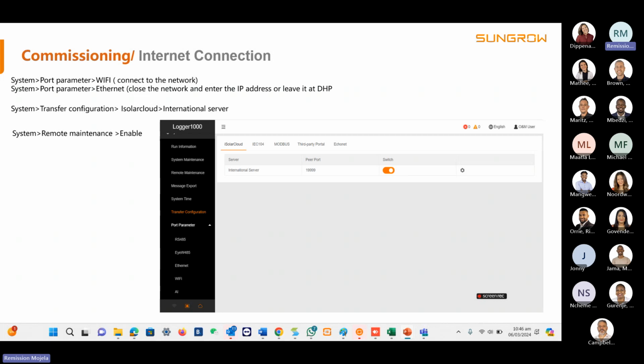So one important thing is that if you just use Ethernet and leave it like that without inputting the IP address, it will automatically be on DHCP. It will pick up an IP address and try to connect to that IP address to give the system internet connection, unless you have a static IP address, in which case you just have to click on the Ethernet and close the DHCP, then input that particular IP address with the subnet mask and the DNS as well, just to be able to get internet connection either way.